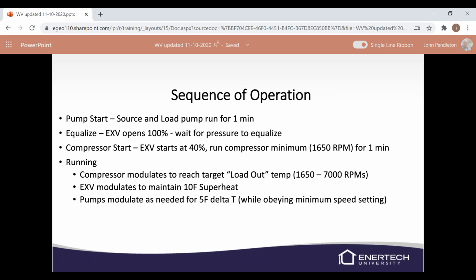So the source and load pumps are going to run for 1 minute. Then it'll say equalize, and your expansion valve is going to open to 100% and make sure that the pressure is equalized. And then you will go and do compressor start. The expansion valve is going to be about 40%, and it's going to run the compressor at minimum speed for about a minute. When it runs in that minute, it kind of is allowing things to stabilize and start to read temperatures and settings and things like that.